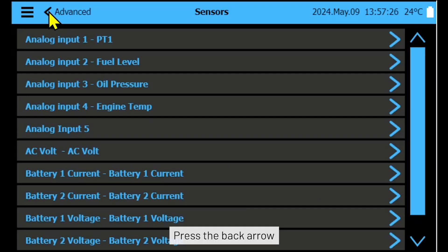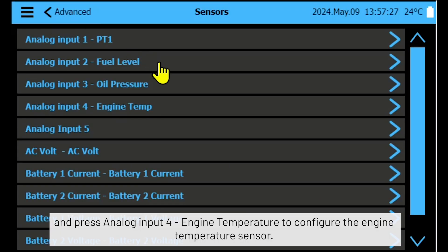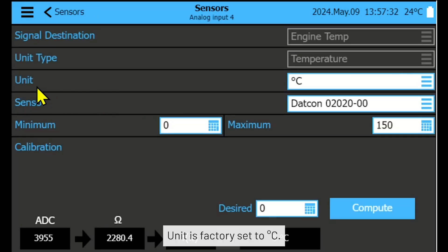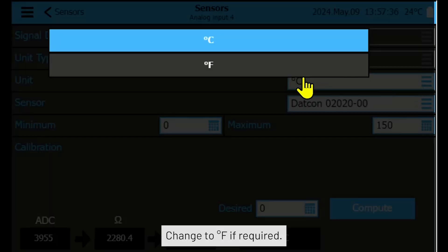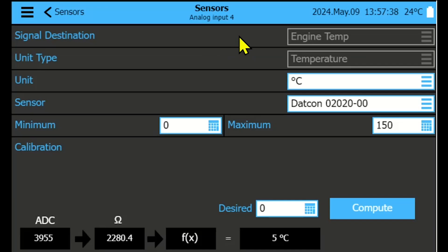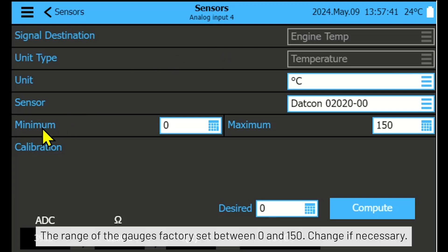Press the back arrow and press Analog Input 4 — Engine Temperature to configure the engine temperature sensor. The unit is factory set to degrees Celsius; change to degrees Fahrenheit if required. The range of the gauge is factory set between 0 and 150; change if necessary.